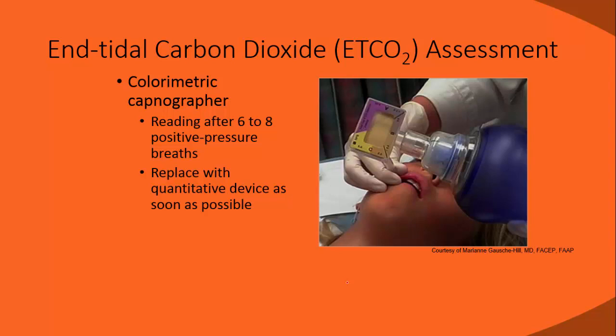Now, to get an initial snapshot, perhaps if your equipment isn't ready for capnography, we can use our colorimetric device, right? We would say that it is proper if we have it placed in the correct location, we should get a change from purple to yellow. And yellow equals yes, it's in the right place. Now it doesn't give us a number, and the reading is good after about 6 breaths or so through the BVM. You do need to replace that with some other device, preferably a device that can give you a waveform, and realize that if this device gets wet, it is not going to work.